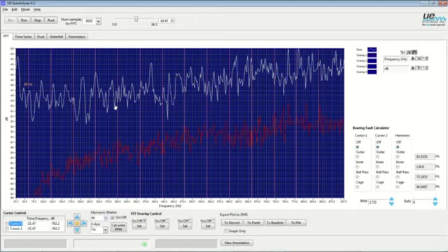One thing I'll call attention to as well was the tonal quality of that recording. If you listen carefully, you could hear pops within that recording, and they were far more pronounced in this recording than the previous recording. So the tonal quality means something as well. And using the FFT here, what I would determine looking at these two spectrums is there's enough similarities looking at the frequency peaks and the noise content in between each harmonic to say they are similar in nature and most likely electrical based on the frequency noise.